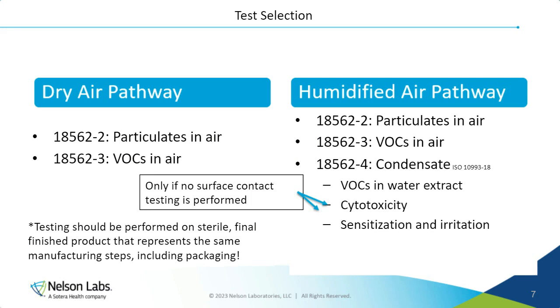But we do want to get into the specifics. So right away, starting with the robust testing, we first have the test selection. Here, we start to build the base of our pyramid. If we have a dry air pathway, we'll just be looking at running a particulate test via 18562-2 and a VOC test via 18562-3. However, if there is a chance that humidified air can be transmitted through the gas pathway, we will additionally look at condensate testing through -4 or ISO 10993-18 for the FDA submissions.